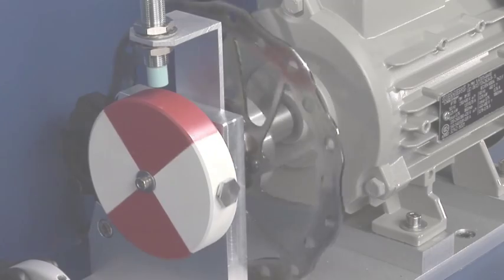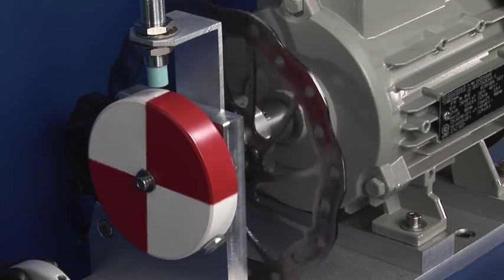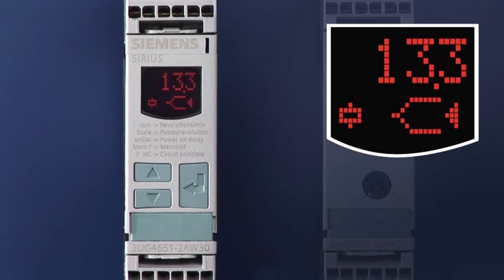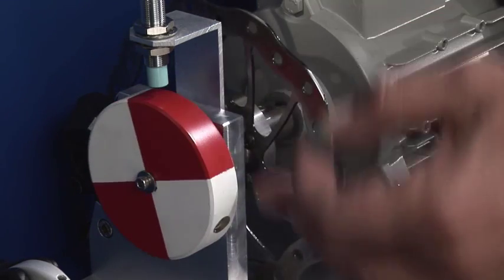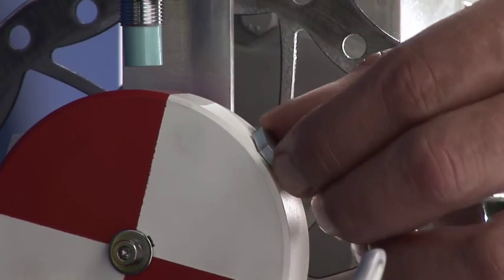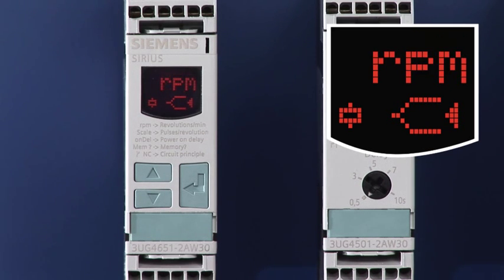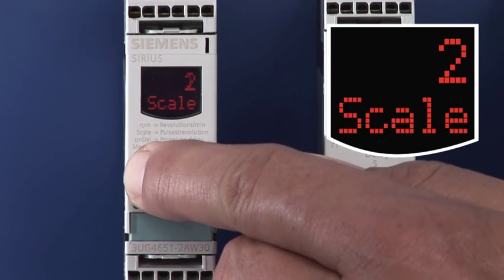With extremely slow rotating motors, a more accurate indication of the current speed is realized by using several pulse sensors per rotation. In this example, a speed of 133 rotations per minute is generated with one sensor. If two pulse sensors are used, the speed apparently doubles. By setting the right scaling factor on the device, the correct values are displayed.